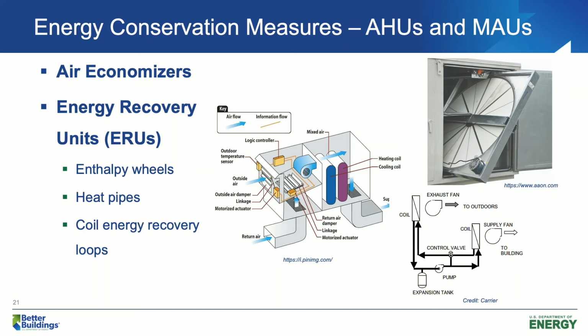Energy recovery units. When it is pretty hot and humid outside, we are taking the hot and humid air into our spaces, but at the same time we are exhausting dry and cool air out. Are there any technologies that we can use to recover some of the coolness and dryness from the exhaust air? Of course there are. That technology is called energy recovery units, or ERUs. There are 3 major types of ERUs. We can use enthalpy wheels, heat pipes, or coil energy recovery loops.